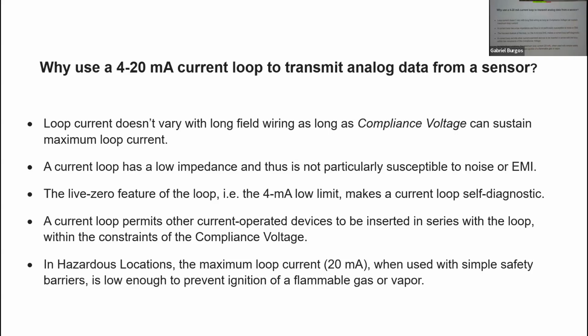And finally, if you're in a hazardous location, oil field or gas field or some other place, this maximum loop current, when you use simple safety barriers, is low enough current to prevent the ignition of flammable vapors. Okay, so you take a voltage device, let's say at 10 volts. If it's not current limited, it could have enough energy to spark the explosion. But the barriers allow you to limit energy involved in the current.